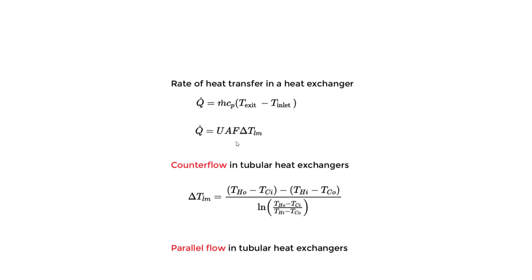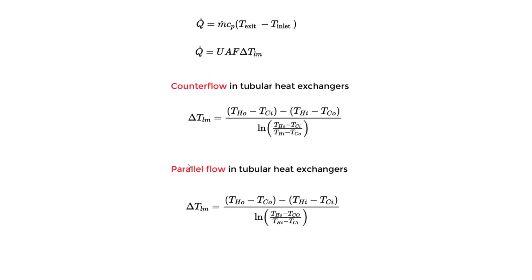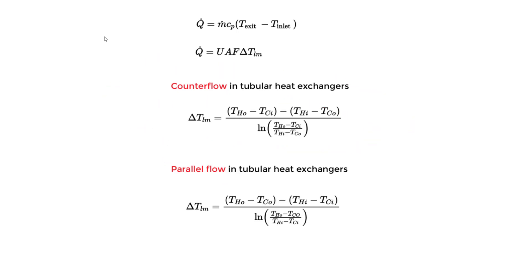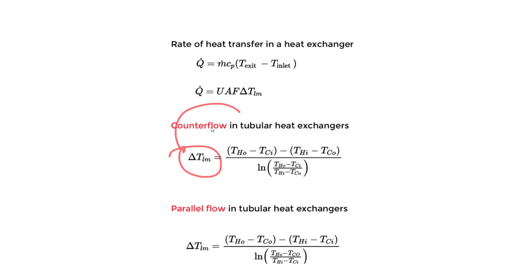The correction factor F depends on the tube arrangement, particularly for shell-and-tube heat exchangers. We assume F = 1 here as noted in the handbook. A is what we're finding, U is known, and ΔT_LM is the log mean temperature difference, which we still need to find. The handbook gives separate counter flow and parallel flow equations for ΔT_LM, so we'll use the counter flow equation, then solve for A.